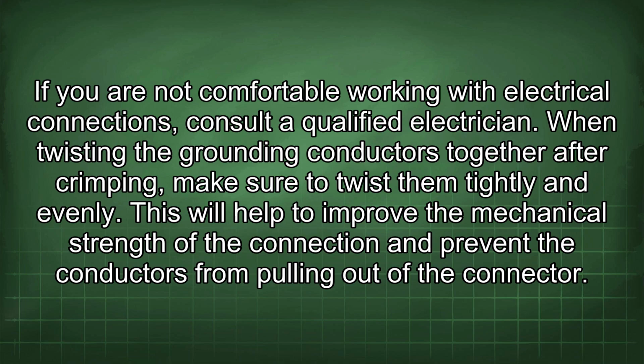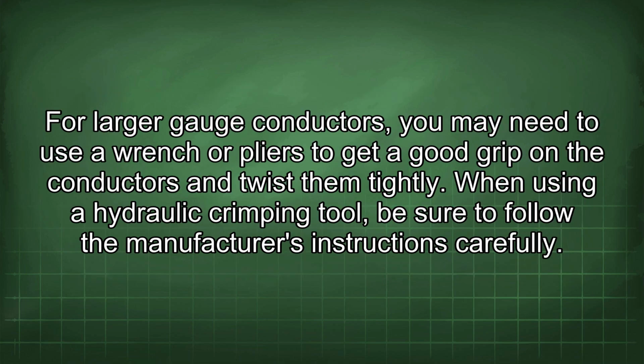When twisting the grounding conductors together after crimping, make sure to twist them tightly and evenly. This will help to improve the mechanical strength of the connection and prevent the conductors from pulling out of the connector. For larger gauge conductors, you may need to use a wrench or pliers to get a good grip on the conductors and twist them tightly.